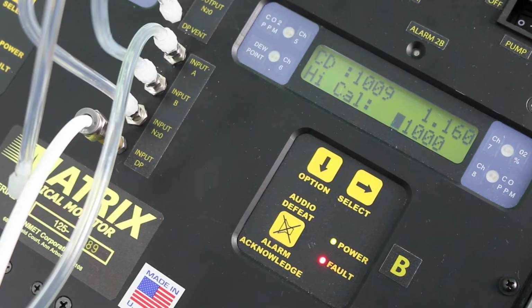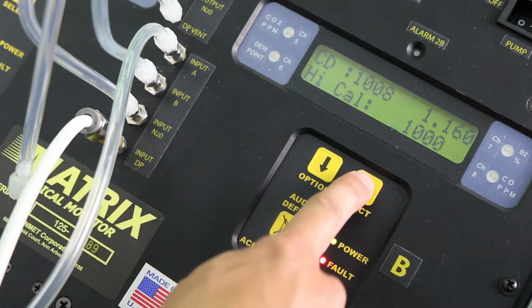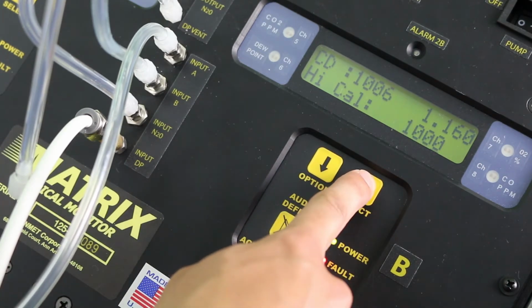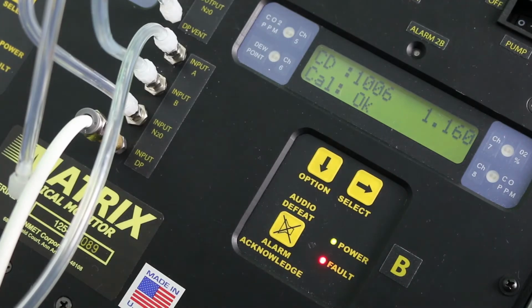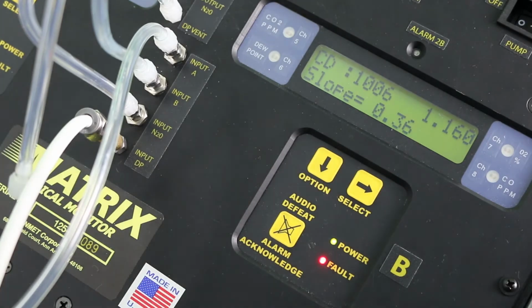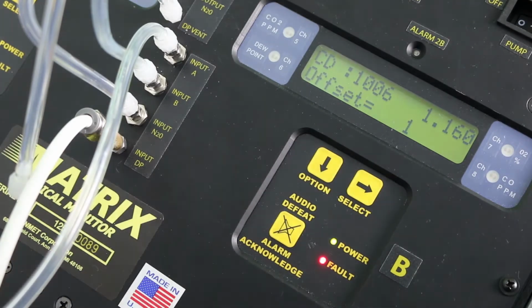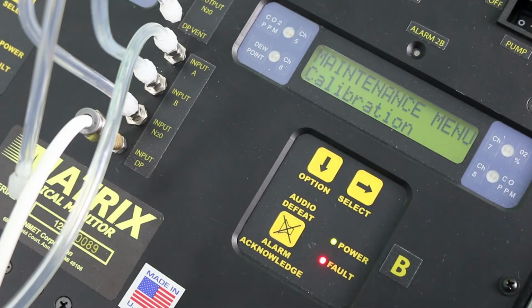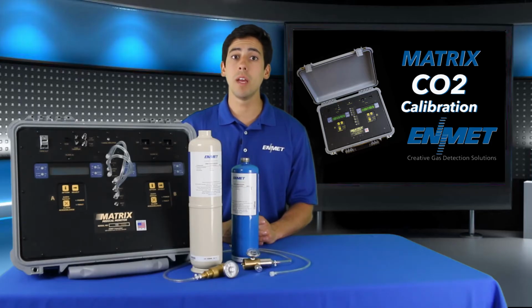To accept the cal, you will move the cursor over by pressing the Select button until Cal OK is displayed. The slope and the offset will be shown after, and it will go back to the maintenance menu. This completes the matrix calibration for CO2.